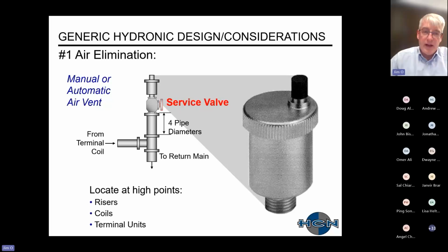This is just a typical detail here, showing your piping coming from a terminal coil. You want to put a little tee, a little pipe diameter, little straight pipe. What will happen is, as the air travels from the coil and through your system, the air will come to that tee and the air will rise. Eventually, that air vent has the ability to remove the air from your system. You want to locate these on risers, basically any high point, and especially on piping mains.